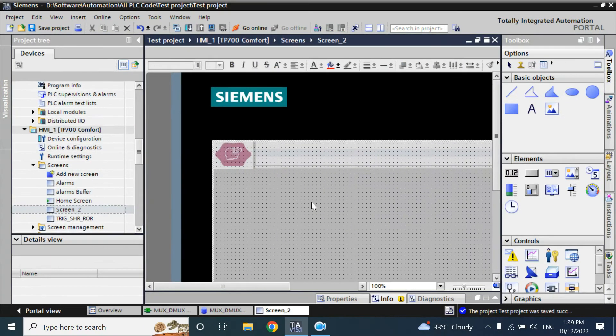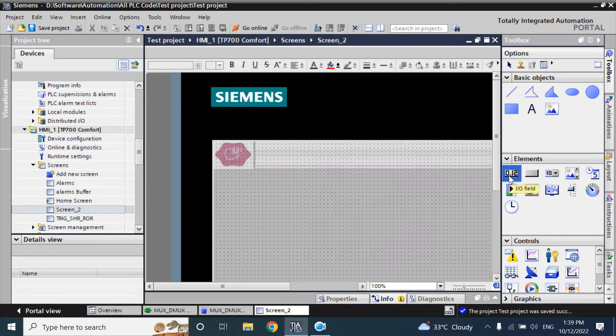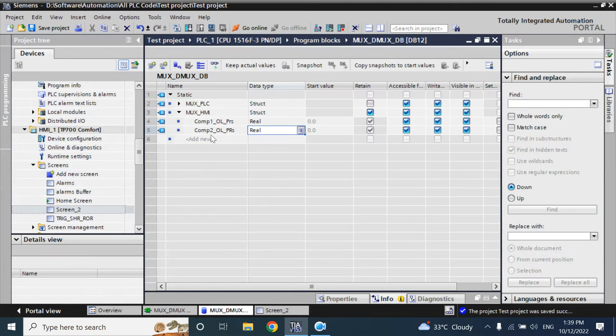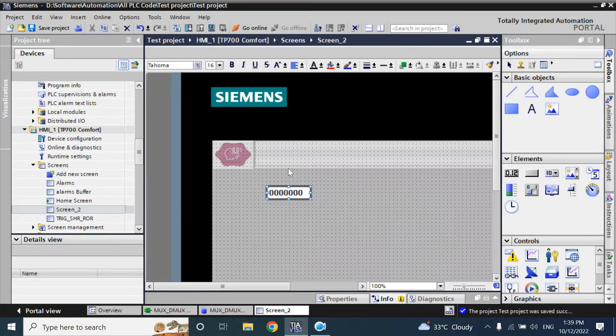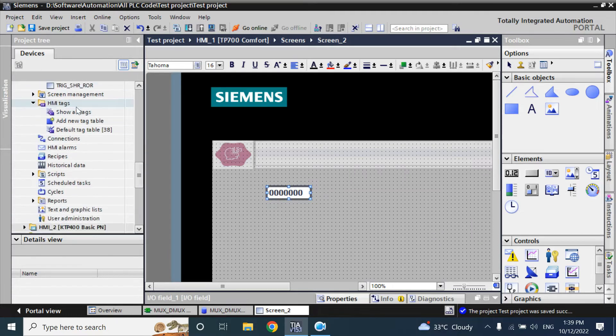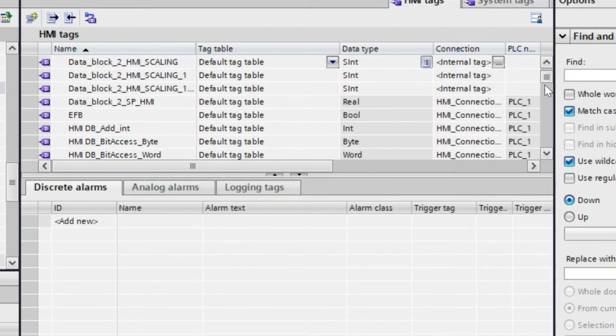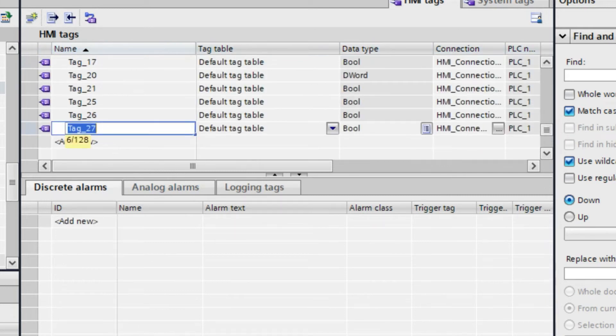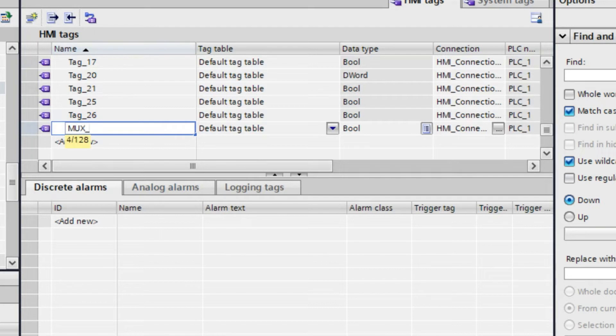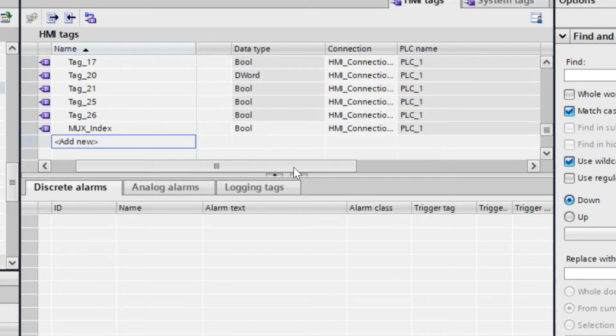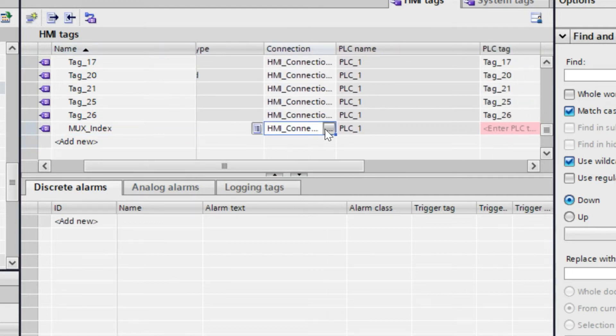In screen 2 we will take an IO field and we will implement multiplexing in that IO field so that our two tags — compressor 1 pressure and compressor 2 pressure — will visualize in only one IO field using the HMI function. Go to the HMI tags. Here we will create a tag called MUX_Index, and that is not from the PLC connection — this is an HMI internal tag.